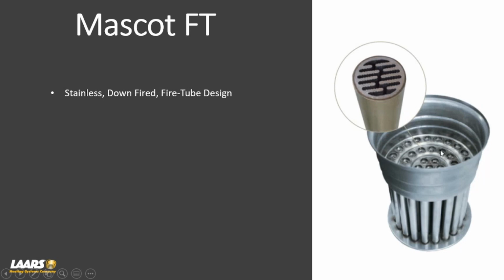And why I bring that up is some manufacturers that have cast aluminum heat exchangers, you have to add inhibitors to the heating system. If you don't, you can destroy the heat exchanger. There is no water on the hydronic side passing through these flues. This is strictly flue gas traveling down and then out in your flue collector and out your vent.